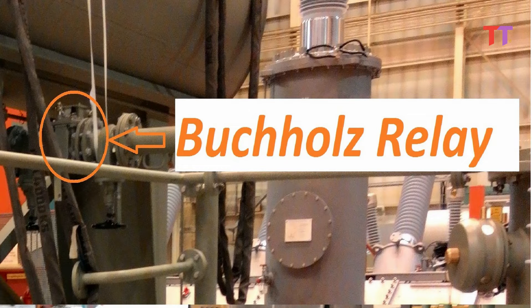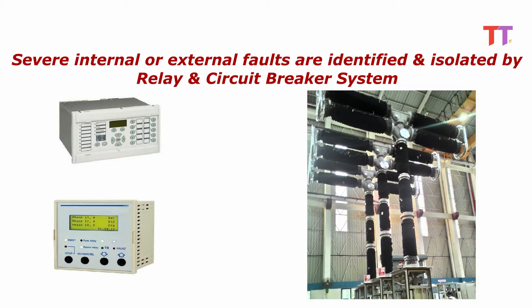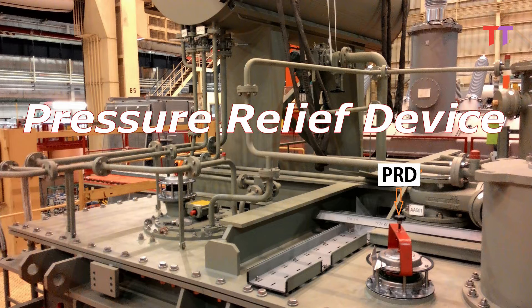Buchholz relay gives an alarm and subsequently trips the transformer in case of gas accumulation due to incipient fault. Also, DGA — dissolved gas analysis — of transformer oil is done periodically to identify any gas formation or degradation of oil. Severe internal or external faults are identified and isolated by relays. Even if all these systems fail, there is a PRD installed on the transformer tank, called as pressure relief device.